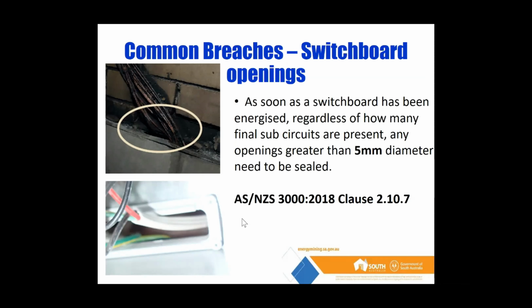There's a good example there in the top photo. You can see this is actually the inside of a house. So imagine the gyprock's been burned off the wall. There was a fire. It's then escaped out of that switchboard and gone up the wall cavity and engulfed the entire premises. So if the slider on that board was pushed across, or someone filled it up with some fire foam, or had a bit of fire-rated insulation that's pushed in the hole, or a pillow, or something simple like that, the fire would have been contained in that switchboard. And then there's just a little photo underneath it as well of one that hasn't caught fire. How simple it would have been to just seal that hole there.